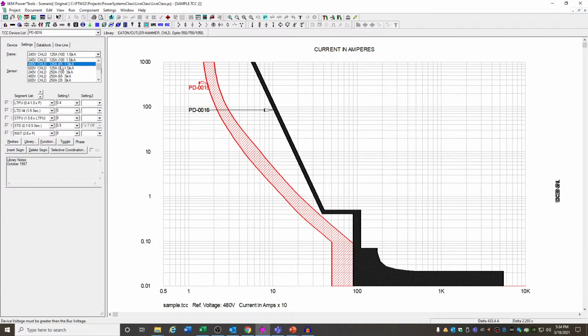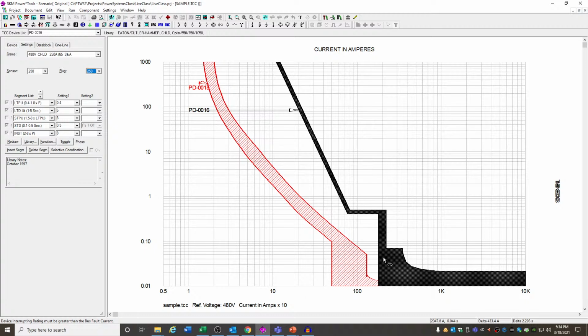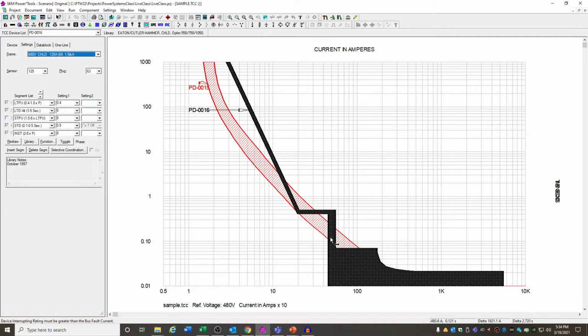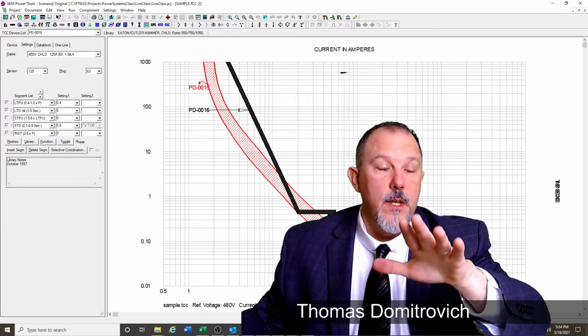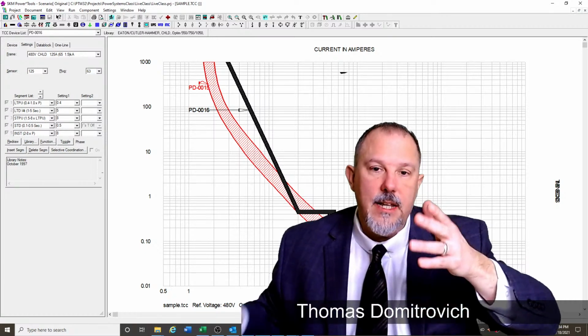That's 240 volt. Let's see, we'll do a 480 volt, 250. There we go, 250. So now I'm moving the instantaneous. So you see what I'm doing. I've increased the size of this from say 125 amps, and look what the instantaneous did. And now I can't get that instantaneous to move any further to the right. Okay, so this is important, because for selective coordination, I need to get separation of curves.